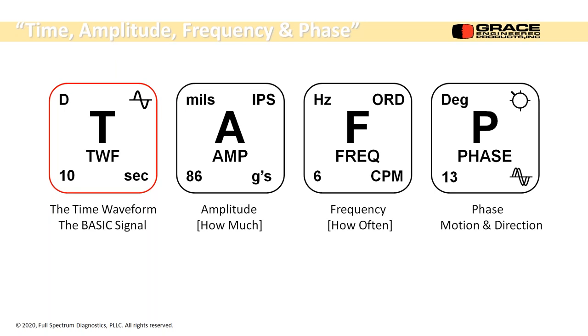Okay, so we're going to get an amplitude out of it. We can trend that velocity signal coming out, but we can also trend, we'll find out in a few minutes, the ultrasonic end of that as well. So the time we're going to look at in a second here. Amplitude is in different units: mils, inches per second, or Gs. The dominant response parameter that we want to look at is velocity in inches per second.